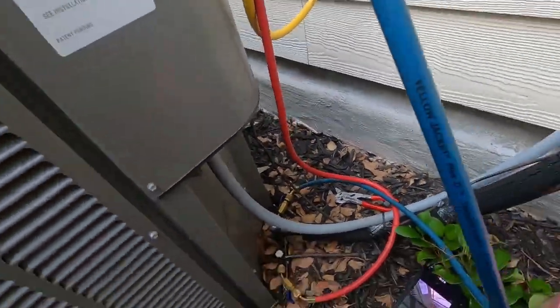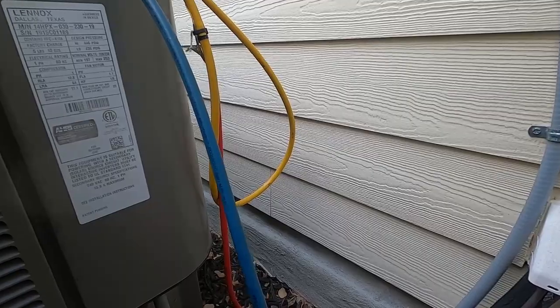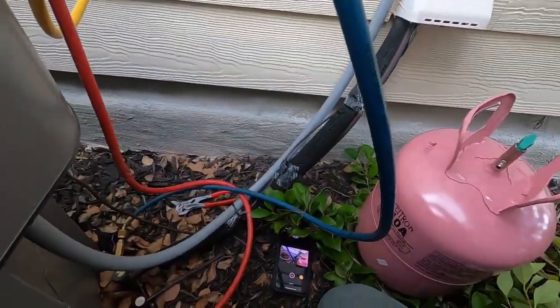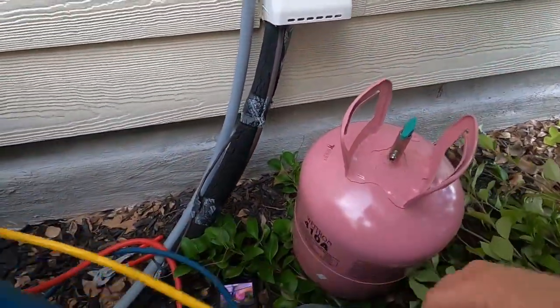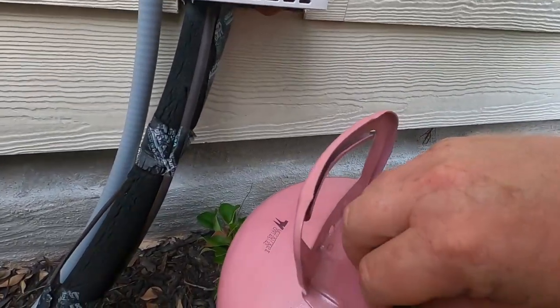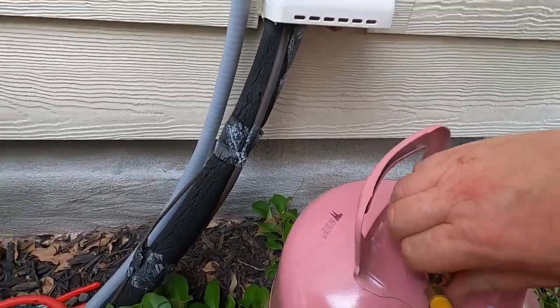Alright, well now we're outside where I can talk and not worry about the tenant hearing what I'm saying. Ain't that some bullshit? Some builder can put that kind of crap in a house in the second floor closet, downflow, Lennox piece of junk air handler. You got no water protection under it whatsoever because it's downflow. So all your duct work is interior to the floor and the ceiling between the first floor and the second floor, meaning all your supply registers downstairs are in the ceiling, supply registers upstairs are in the floor.